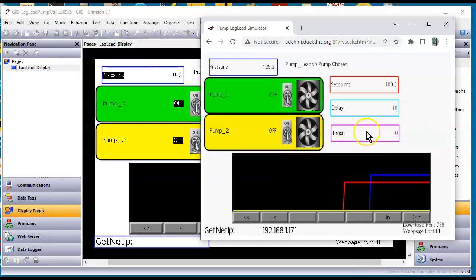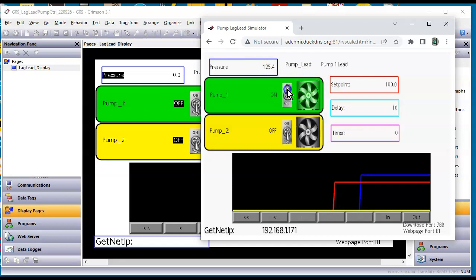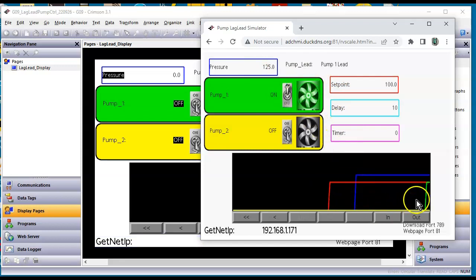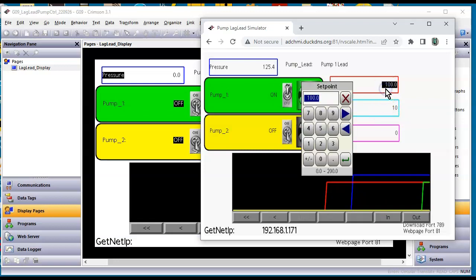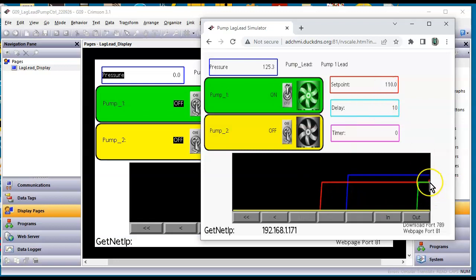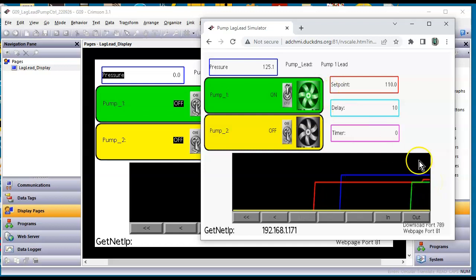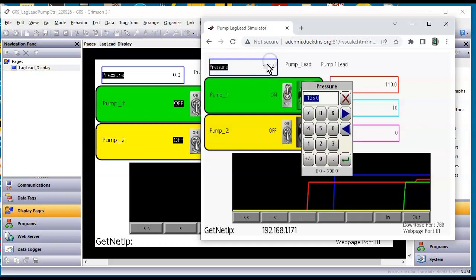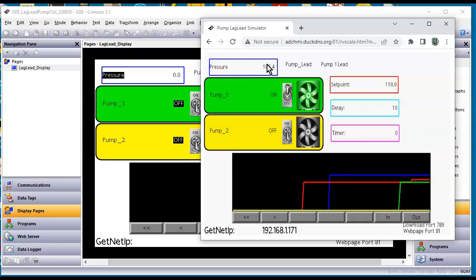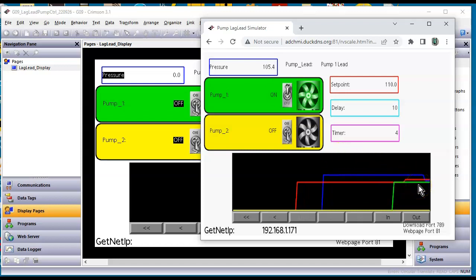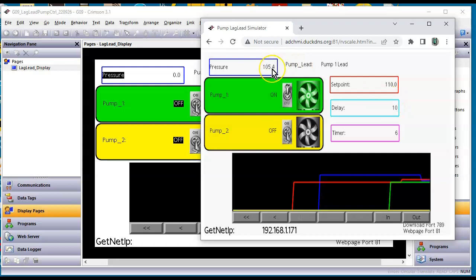Anyway let's go back to our demo here. So here it is running. You can see the pressure's at 125. My set point's here. So if I turn on my pump one you can see the pump one's on. You can see here I've got, let me raise this up a little bit higher just so that we get a different line here on my chart. Okay so there you can see that. Now if the pressure drops below the red line it should fire up pump number two. So if we put this at say 105 for instance we'll see the blue line just dropped a little bit below there.